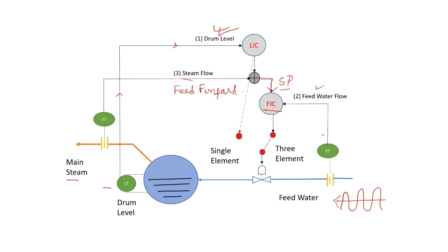So now we have all the three elements: drum level, feed water flow, and steam flow. When all three elements are taken into consideration, this whole control scheme acts more robust and less susceptible to variations in feed water or main steam flow or any disturbance in the process.